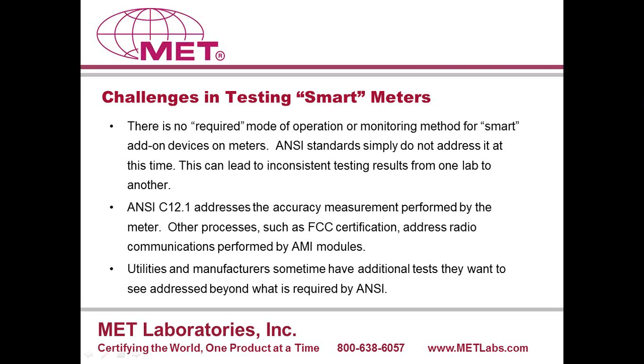So there's no specific required mode of operation. I mean, you have such an array of different types of products anymore that we're trying to apply this standard to and prove that the accuracy is good to a certain percentage. It may be a class 1, class 2 type accuracy, 1%, 2%, or it may be a tighter accuracy in the 0.5% range. No matter what, we're trying to formulate test programs around that product and apply the ANSI requirements to it. We're very successful in doing that. It's been very successful and has benefited our customers greatly. But it is a challenge to do in many cases, and there's no one magic answer for the mode of operation of any particular product.